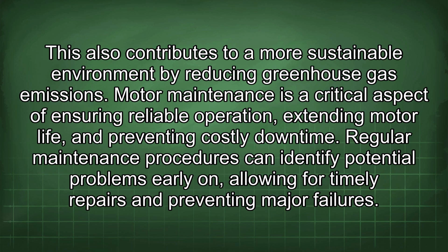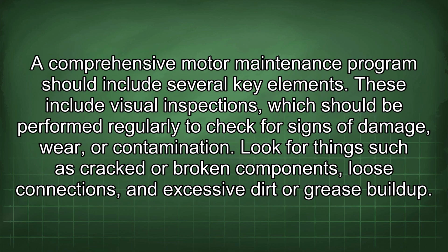Motor maintenance is a critical aspect of ensuring reliable operation, extending motor life, and preventing costly downtime. Regular maintenance procedures can identify potential problems early on, allowing for timely repairs and preventing major failures. A comprehensive motor maintenance program should include several key elements. These include visual inspections, which should be performed regularly to check for signs of damage, wear, or contamination. Look for things such as cracked or broken components, loose connections, and excessive dirt or grease buildup.